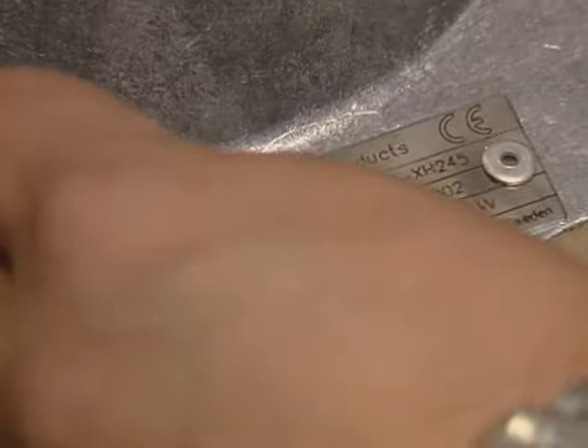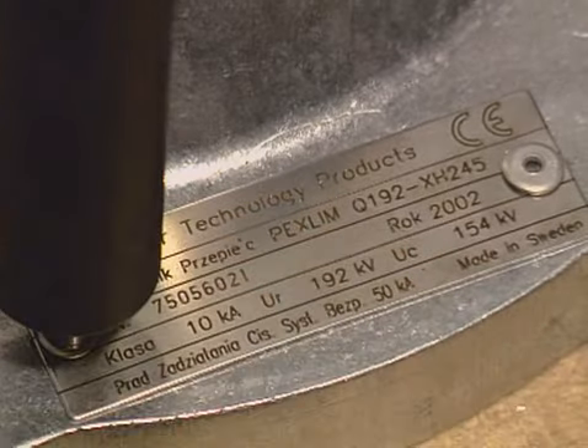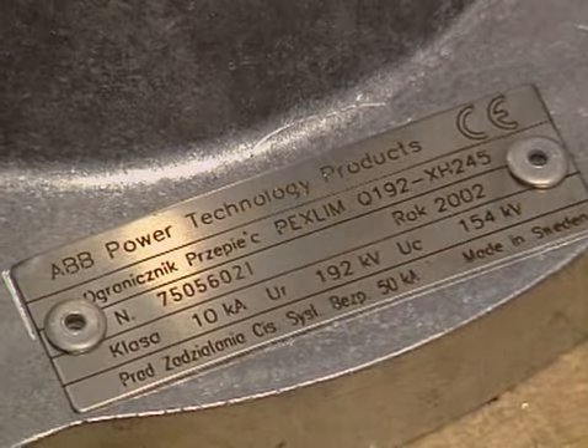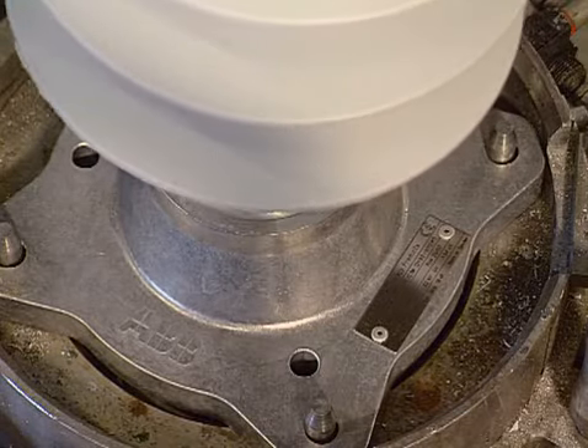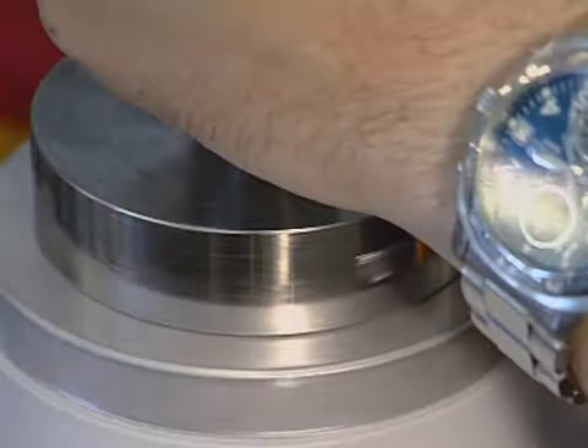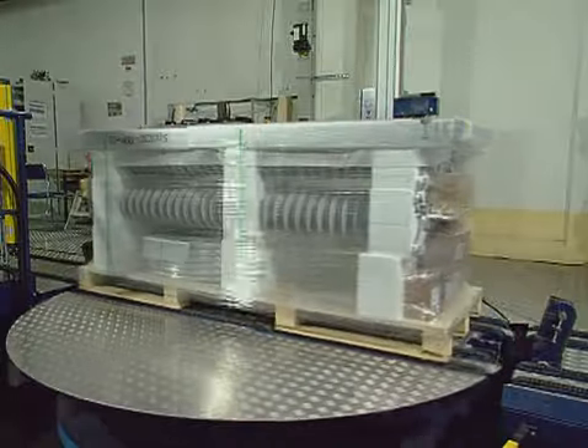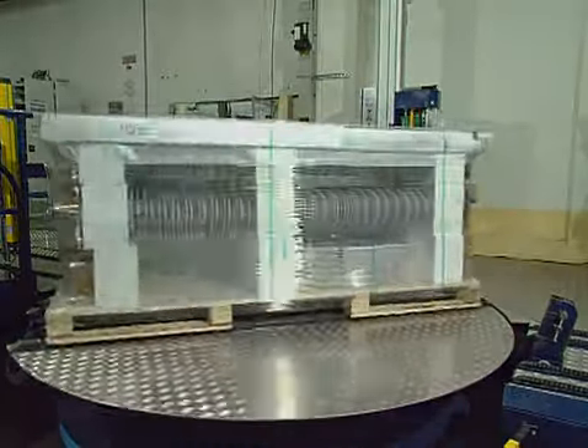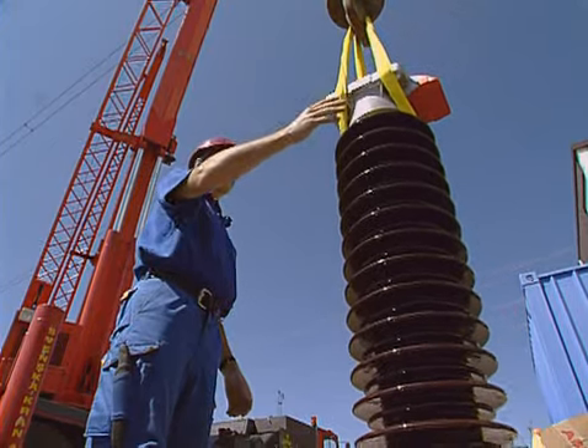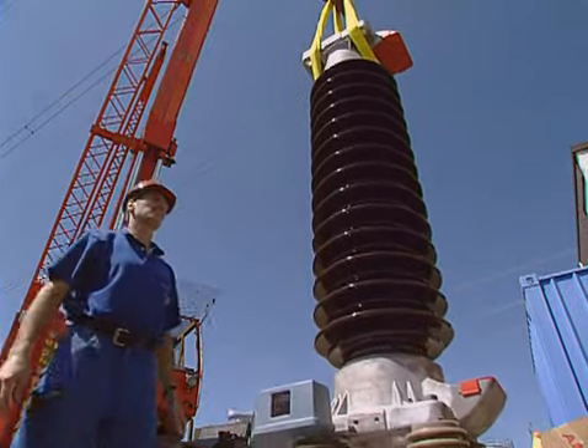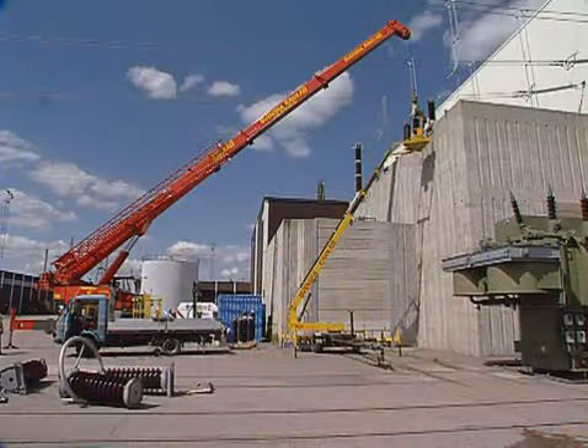Each unit is marked with its individual electrical design to ensure that they are mounted in the correct order when several units are connected in series. This marking follows the applicable IEC standard. Packing material is environmentally friendly. ABB's arresters are simple to install and require no special tools.